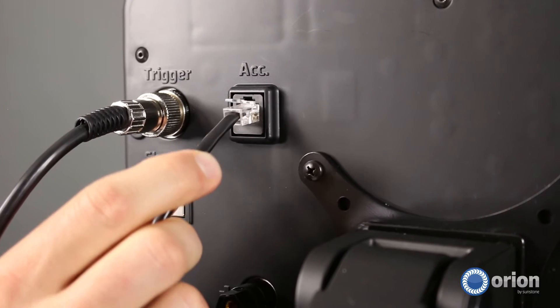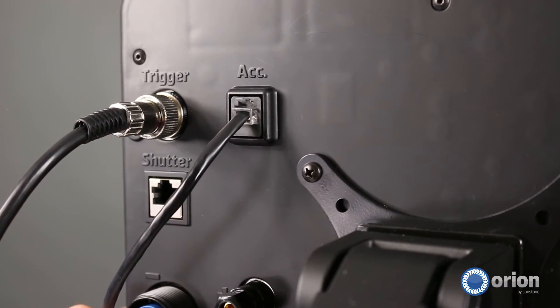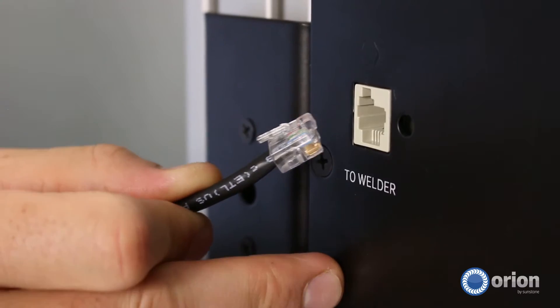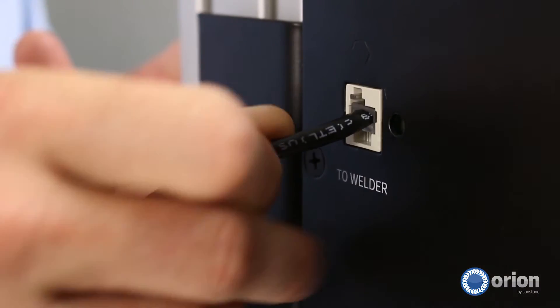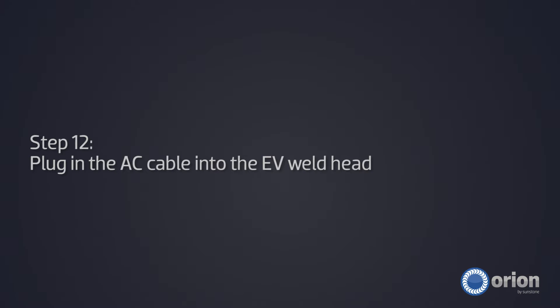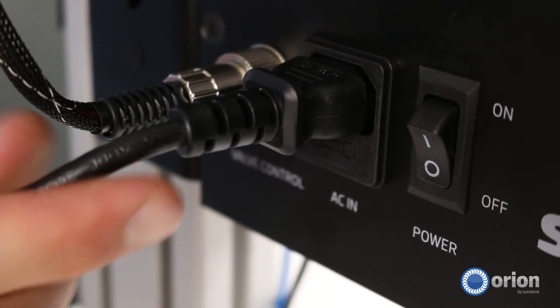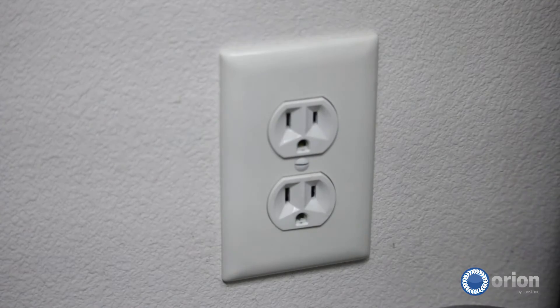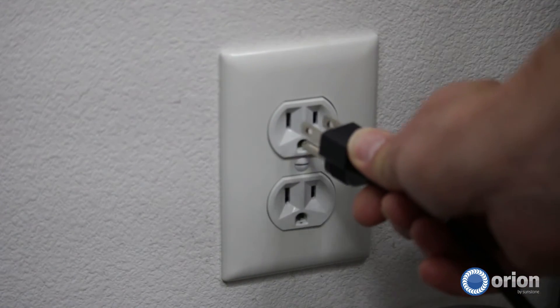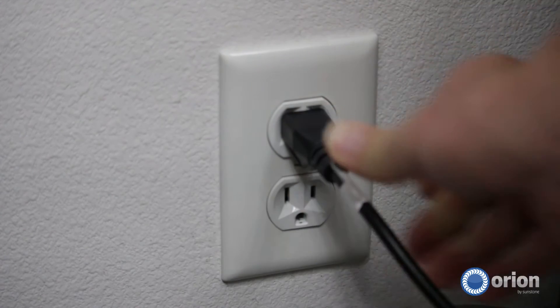Plug the RJ45 end of the cable into the welder and the RJ11 end of the cable into the weld head. Plug the AC power cable into the side of the weld head, then plug the other end into any standard 110 to 220 VAC outlet.